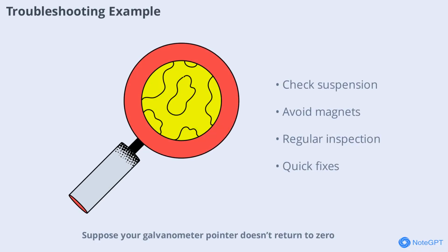Suppose your galvanometer pointer doesn't return to zero. This could be due to a twisted suspension wire or magnetic interference. Carefully inspect the device, straighten the wire if needed, and ensure there are no strong magnets nearby. Regular troubleshooting keeps your instrument in top shape.